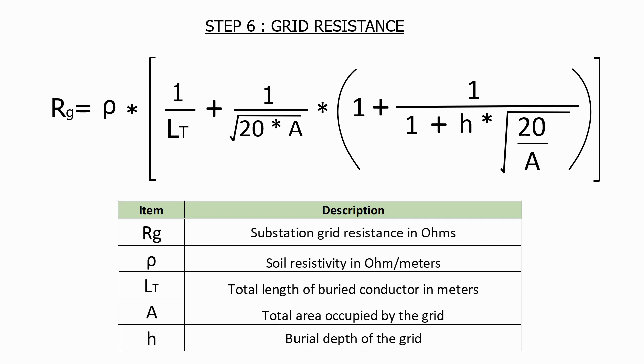Here's the parameters within the formula. Rg, which is the substation grid resistance in ohms that we're trying to find. We have ρ (rho), which is the soil resistivity in ohm metres. Lt, which is the total length of buried conductor in metres. We have A, which is the total area occupied by the grid. And finally we have h, which is the burial depth of the grid. Now that we have a base design from our grid, all of these parameters can be easily calculated.